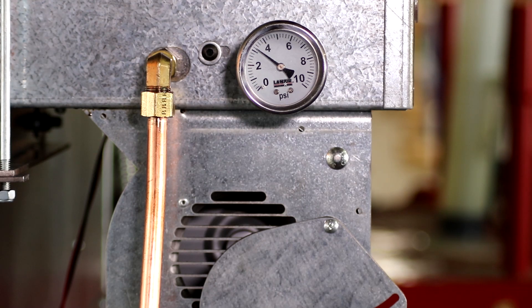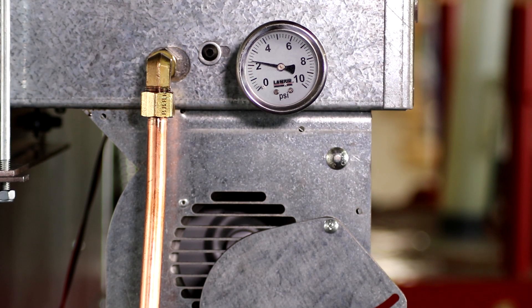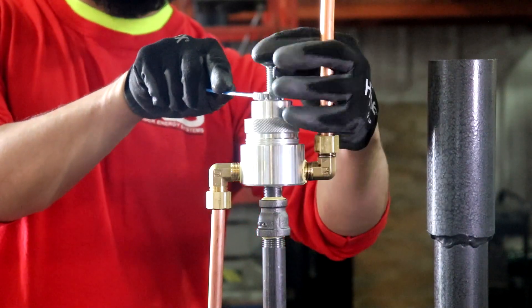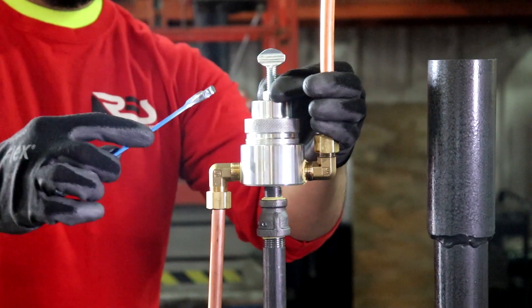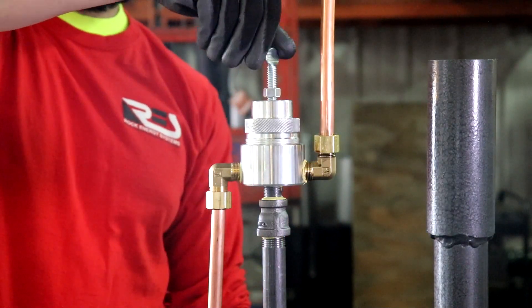You may also notice that the ash produced by an over-fired flame is a dark brown or sooty black in color. If an oil pressure bypass regulator is present on the unit, reduce the oil pressure in 0.1 pound increments until the flame is correct, or down to approximately 1.5 pound below the recommended pressure range for the model, whichever comes first. To do this, loosen the locking nut on the oil pressure bypass regulator and turn the thumb screw counter-clockwise to reduce the flow pressure.